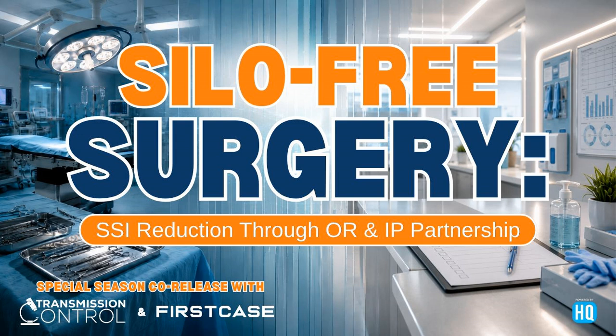So when we think about volume, I imagine every technician, if they only had 6 instruments to do every day, would come out perfect every single time, I would hope. But then we hit the real world. So I'm curious, when going through the validation process, if you find that under worst case conditions there's a failure, and definitely correct my language if I'm not describing this correctly, but if you go through the IFU and find that it doesn't cut muster, it doesn't get us to the 6 log reduction after going through everything, what's the next step? Do you send that back to the manufacturer, or how does that work?